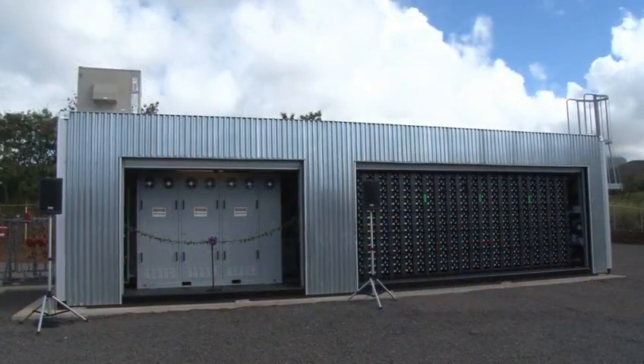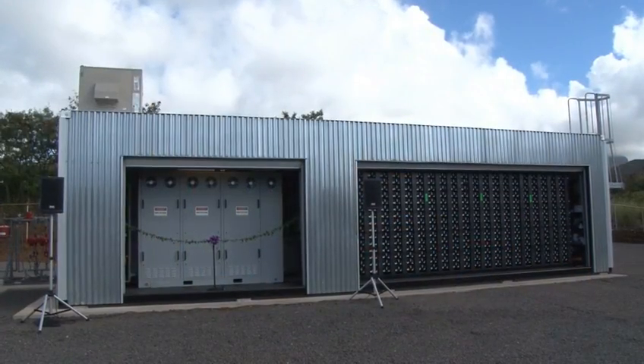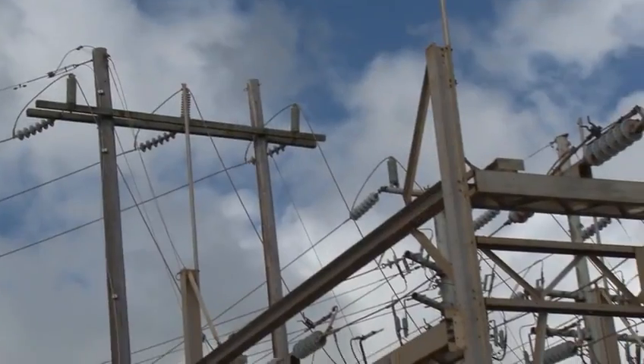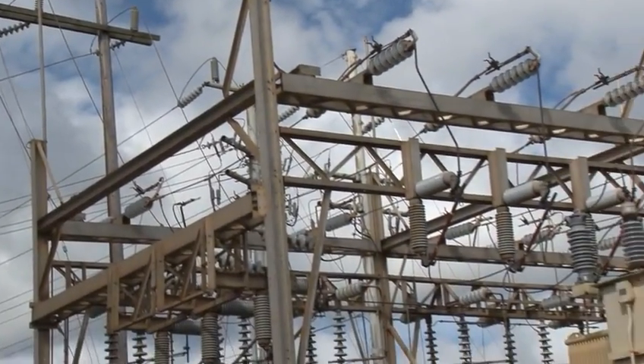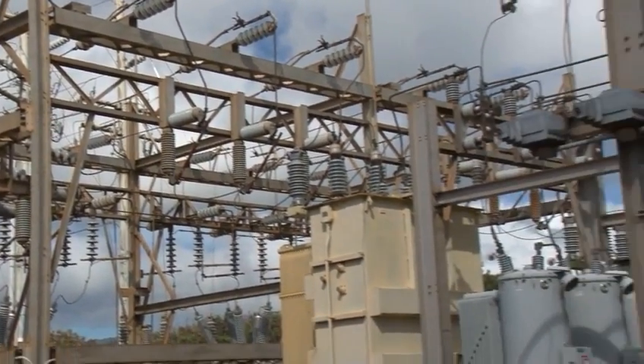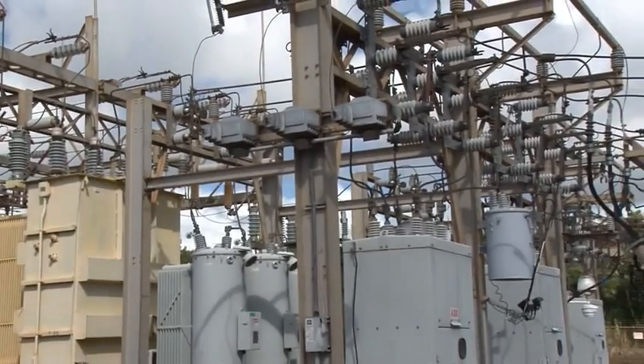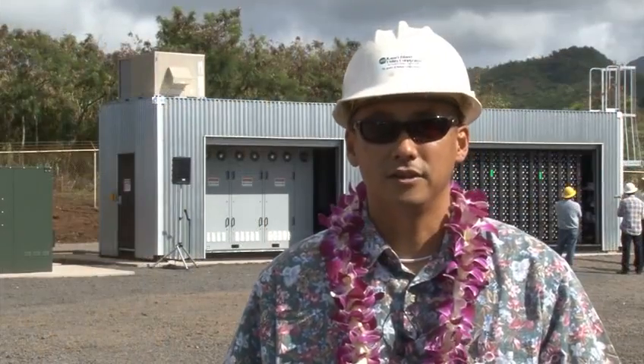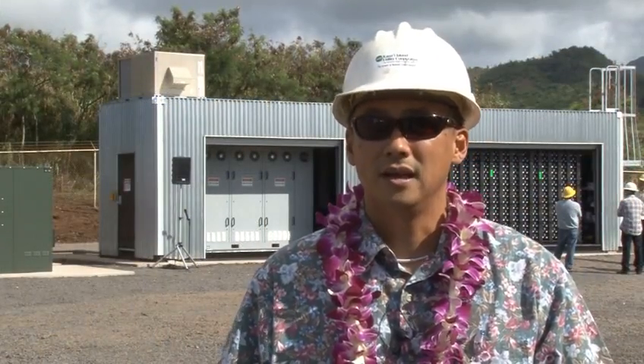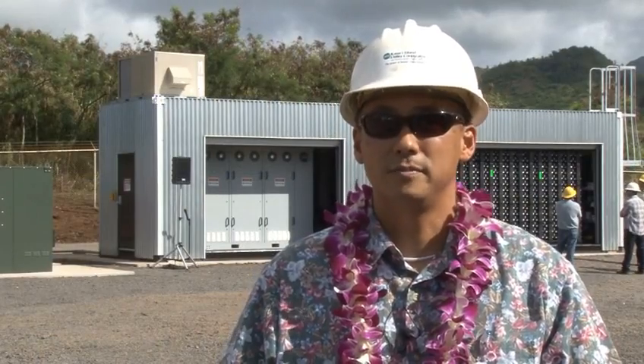This storage system is a 1.5 megawatt battery. The whole goal of this system is to be coupled with a 3 megawatt PV farm that's going to be located about a mile down the road. This battery is going to support that PV during cloud cover, any intermittencies, controlling the ramp rate. But the dual benefit of this battery is also to support our grid.